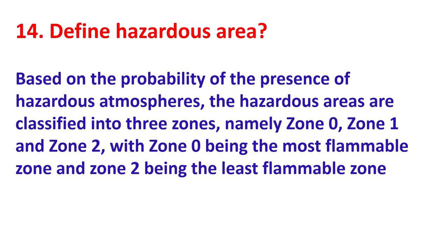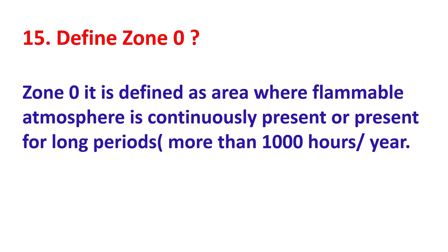Define hazardous areas. Based on the probability of the presence of hazardous atmospheres, hazardous areas are classified into three zones: Zone 0, Zone 1, and Zone 2 — Zone 0 being the most flammable zone and Zone 2 being the least flammable zone. Zone 0 is defined as an area where a flammable atmosphere is continuously present or present for long periods, more than 1000 hours per year.